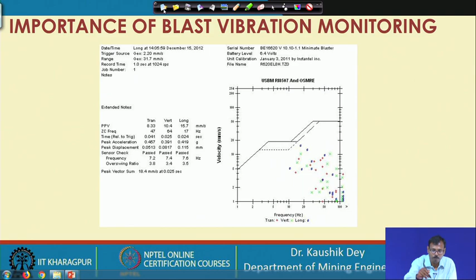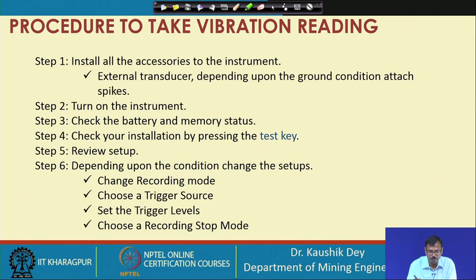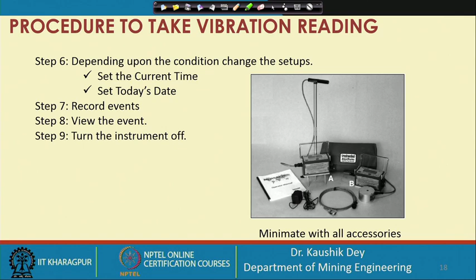The procedure to take the vibration is: install the accessories and instrument, then turn on the instrument, check the battery and memory status, check the installation by the test key, then review the setup, then give the instruction to the instrument. The time and date setup has to be done, then the events will be recorded, and finally the recorded event will be transferred to the computer and viewed, or further analysis may be carried out in the computer software.